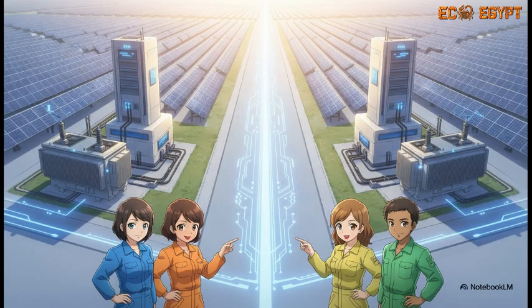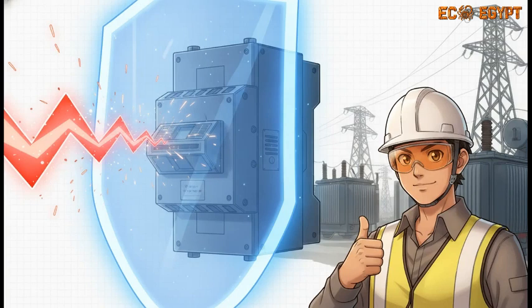Now, what's really interesting here is the perfect engineering symmetry required at this kind of scale. The plant is perfectly bifurcated. Station 01 and Station 02 are basically identical twins. Each one handles exactly 15 inverters, exactly 3,300 modules, and 2.046 megawatt peak of DC capacity, feeding into matching 2,000 kVA or 2 MVA transformers. This perfectly balanced design drastically simplifies your maintenance and ensures highly predictable thermal dynamics as all that power steps up to 11 kilovolt. But of course, with that much power comes the need for incredible safety measures.